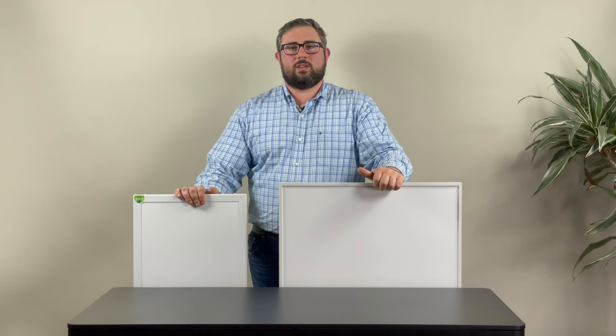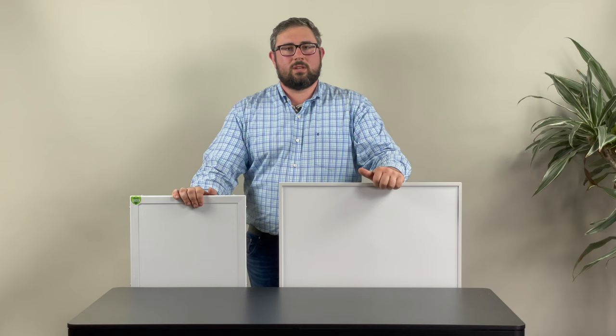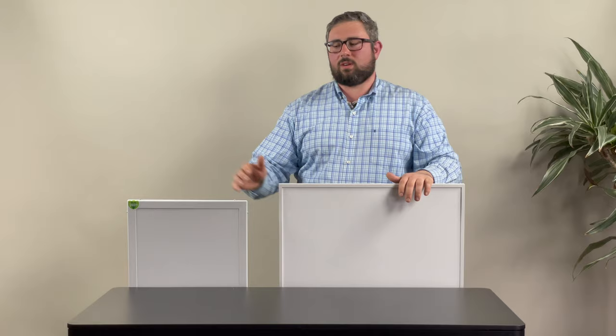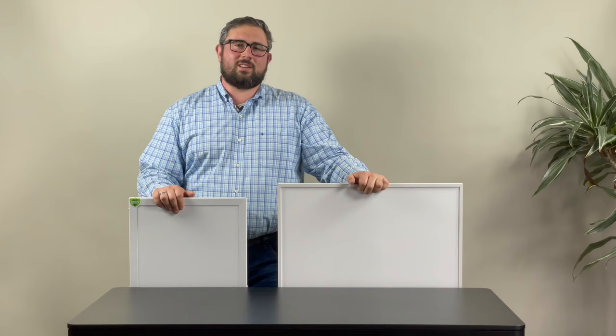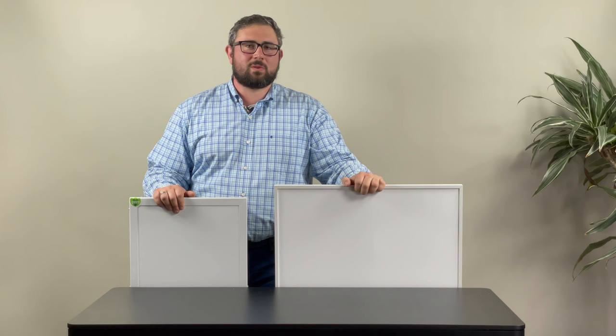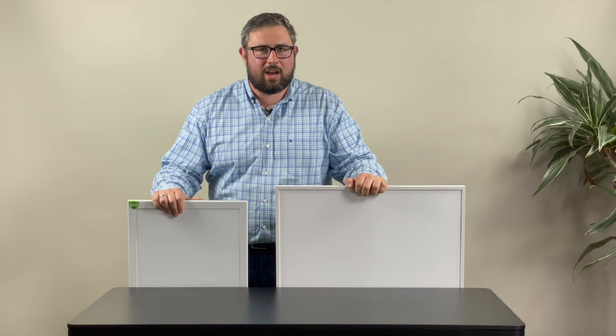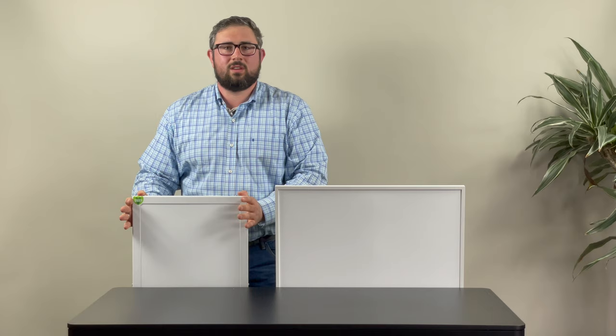The next part is the installation process for each of these panels. The electrical connections on the back are the same—it takes the same gauge wire and they're very similar in terms of the amount of time it takes to affix a panel to your ceiling. However, carbon fiber-based panels are a lot more expensive to install. The reason is you need a lot more of these to get to a desired temperature. The measuring stick for how hot your studio will reach is not based on the quantity of panels; it's based on the total wattage or the output of all the heat combined pouring into your studio. When you have a panel like ours that is higher wattage, you need fewer panels to reach that finish line.